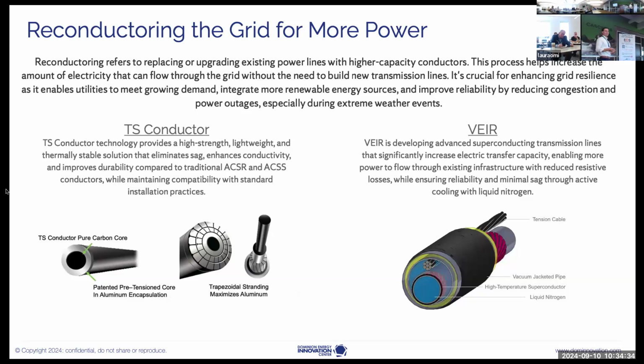But there's opportunity there. Technology has come a long way, wiring has come a long way, our understanding of composite fibers has come a long way. So TS Conductor set out in 2018 to bring to market a composite core with a new type of aluminum design encased around it, to move 30 to 40% more electrons down the same right of way on transmission lines. Reconductoring is fundamentally about taking infrastructure you've already built, the towers and right of ways, and putting new lines down them that let you move more electrons through that same area. It's pretty simple, we're upgrading the pipe we've already put there because we need to meet this electrification.